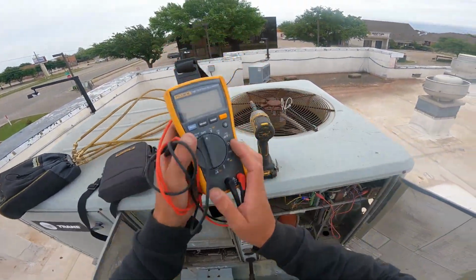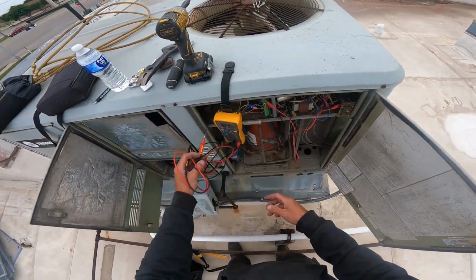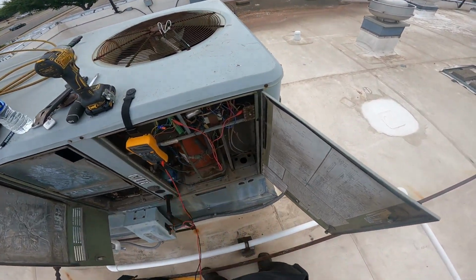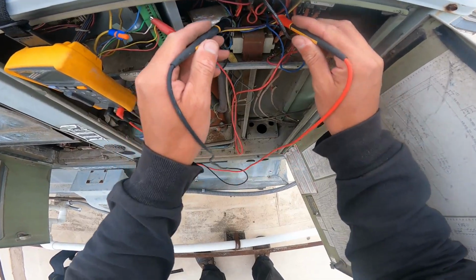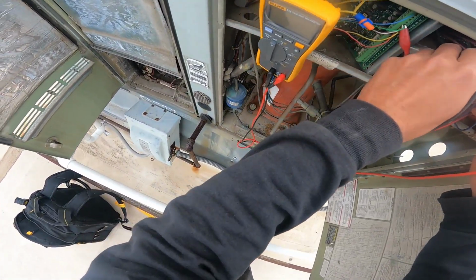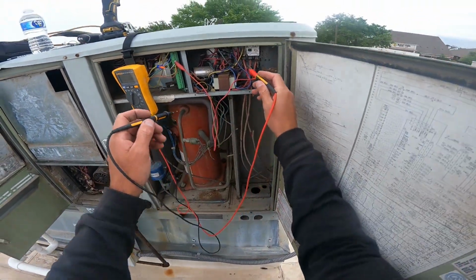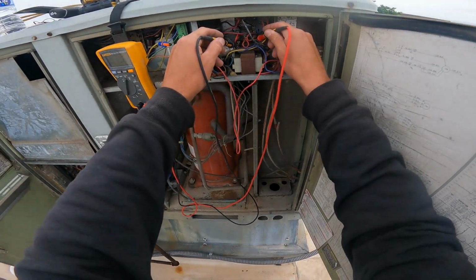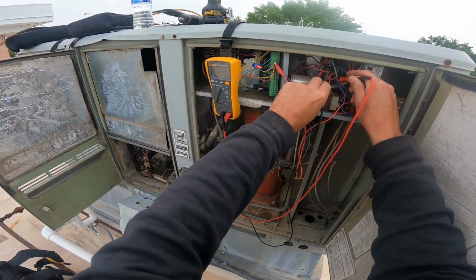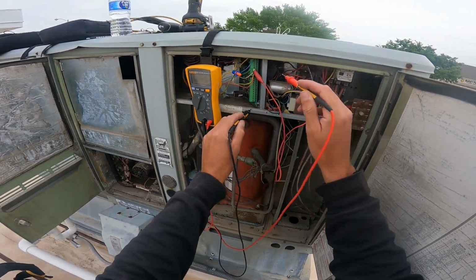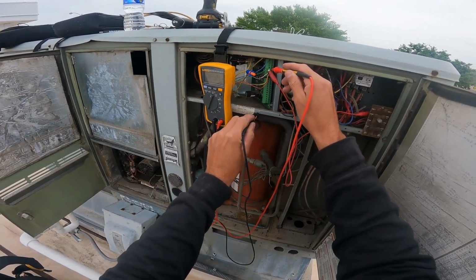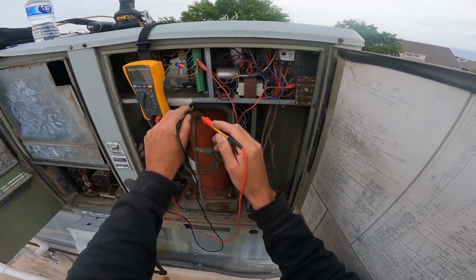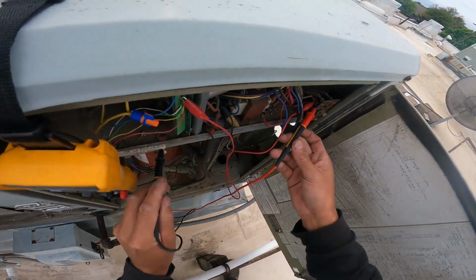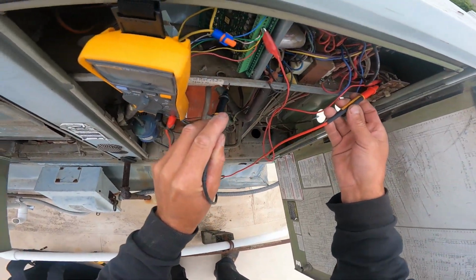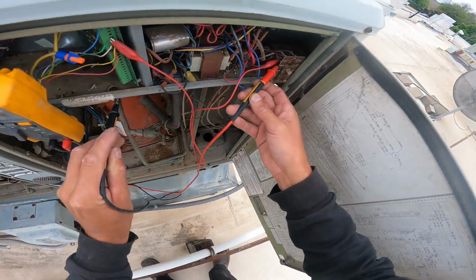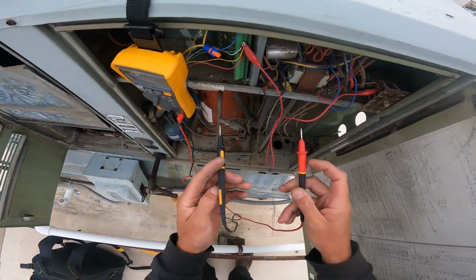Blower's not coming on. So the next thing I need to do is check the blower relay, which could be the one that was disconnected, and find out if that relay is getting 24 volts to the coil. If it is, then it's obviously a bad relay. And you got to turn your meter on first, Matthew. Come on now. There's 1, 2. There is no 24 volts going to the coil. And, well, I don't even have 24 volts coming to my, that means I don't have 24 volts coming here. I do have 24 volts here, but it's not making it to here.